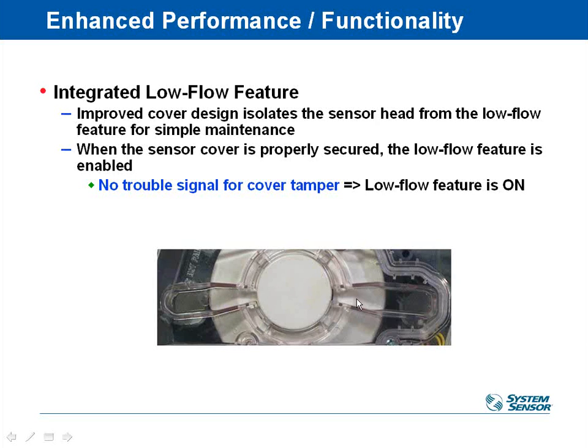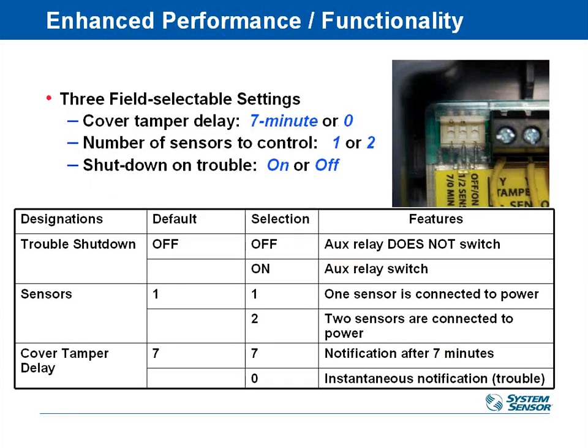to give us a higher velocity actually through the detector itself. So that's one of the ways we can get low velocity air systems to be detected by the standard detector. There's not a lot to configure on these guys. There's a few dip switches on there. There's a dip switch to tell it, do I have 1 or 2 detectors on this air handler? Do I have a supply and return, or do I just have 1?